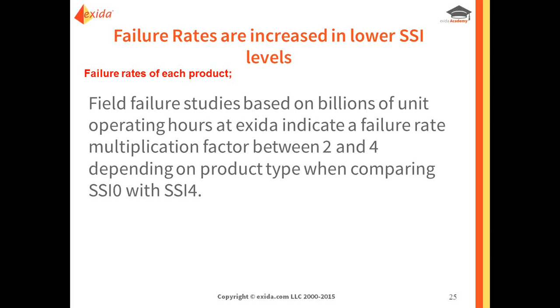Okay. What happens with the actual proof test interval? In site surveys already done by exida, it was apparent that proof tests were postponed in sites where a high level of operational discipline was not present. So if someone's not over the back of that person saying, hey, we need to make sure we do this proof test, we can do it later. Everything's working fine. It's a critical time. It's the end of the month. We need to get this done. We'll postpone it again. Things were getting postponed, and because of that, your proof test intervals are increased. All right, and if they get increased, you're going to start seeing a lower SSI level.